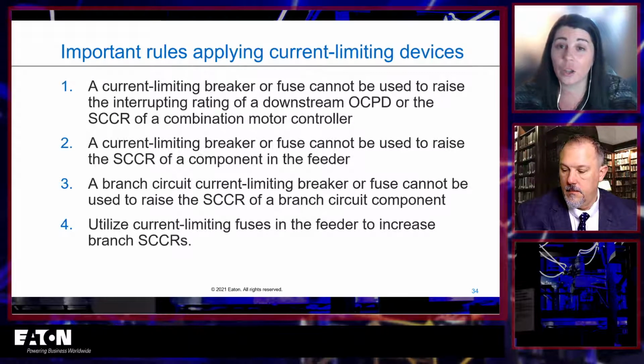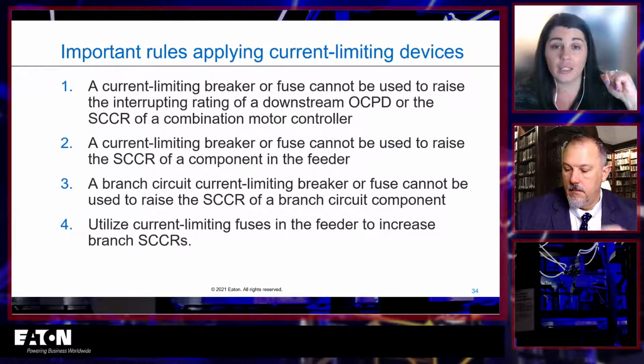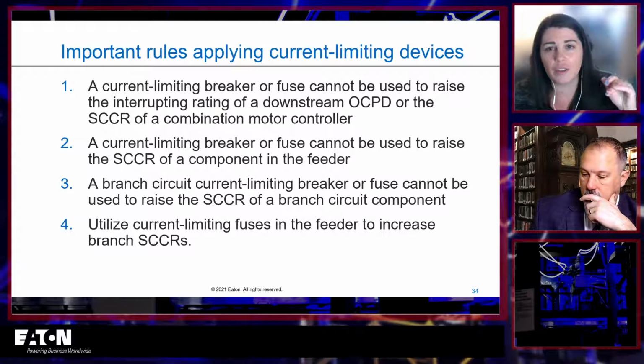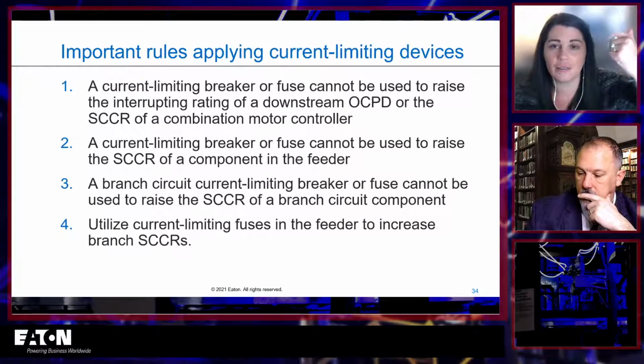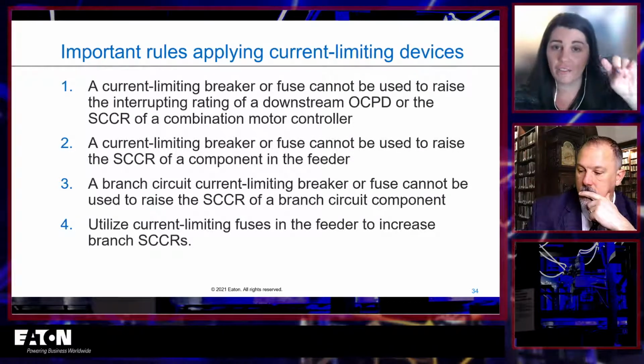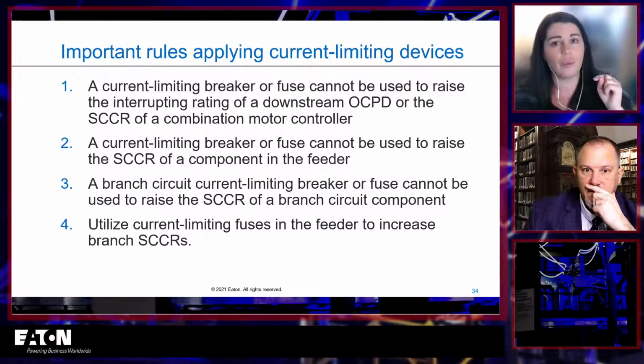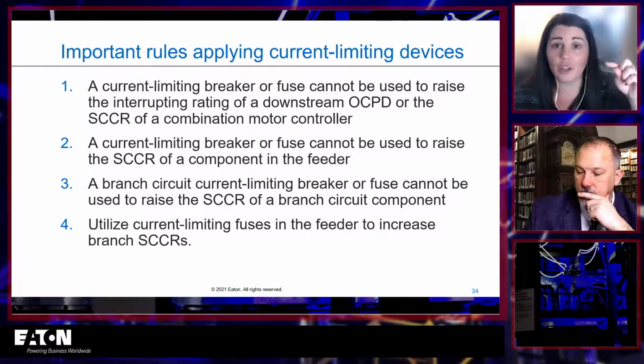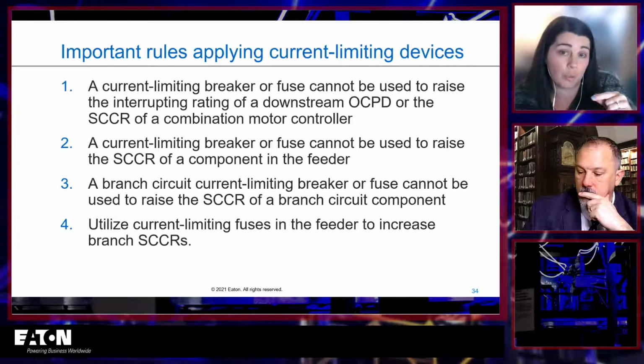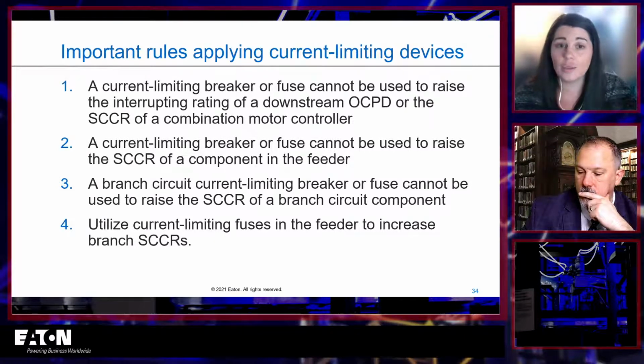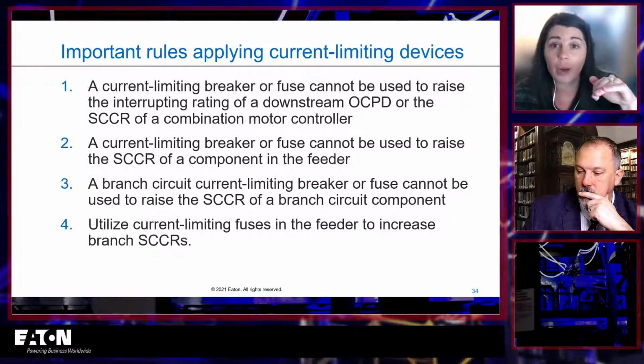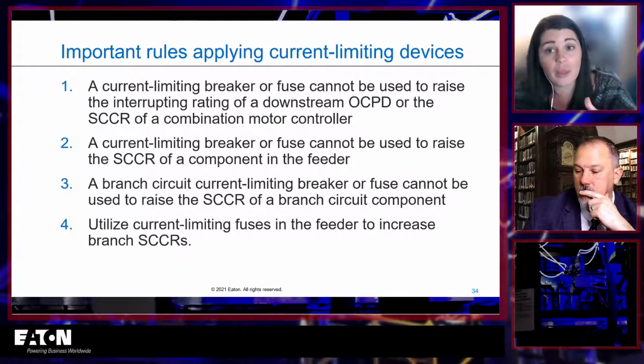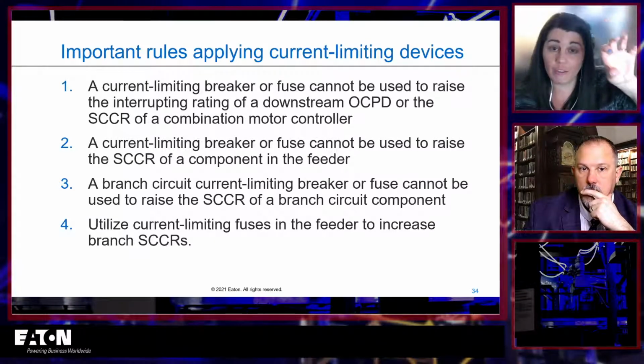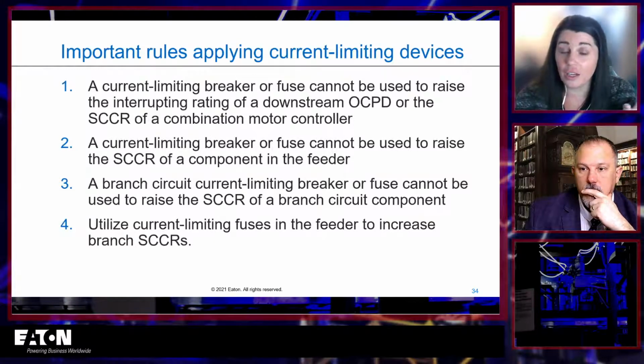So it's important that this is not using a device in the feeder. And really, the easiest way to think of feeder is like your main, of your panel. So it's not something in the feeder helping something in the feeder. It's not, for example, saying that I have a current limiting fuse and it's helping my power distribution block. That's not how we get to use this. And it's not a device in the branch. It's not like I have a fuse in my branch helping the rating of something else in my branch. This only works for a current limiting fuse in the feeder, increasing short circuit current rating in the branch.